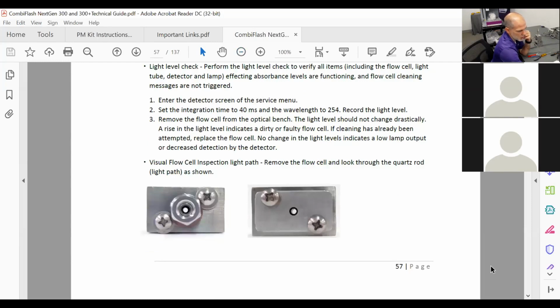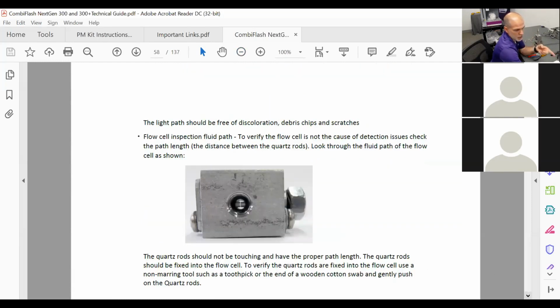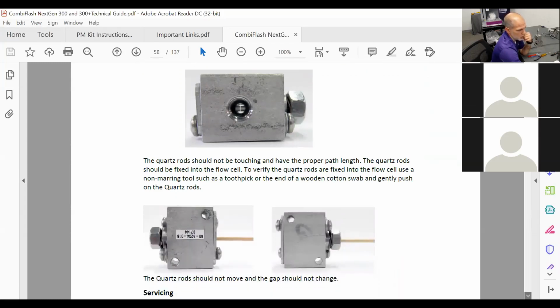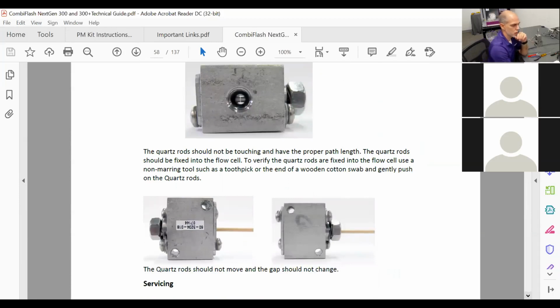Now what I'd like to do is these next couple parts here talk about how to take your flow cell out, how to check it. There you can see the gap in that picture. It's very small, it's 0.1 millimeter, but you should be able to see it with your eyes. All right, it's showing you how to press upon them with a Q-tip here or a wooden stick. And the reason for that is these rods are held in place with a glue. So if that glue has come apart or cracked or dried out, then these rods can move. Pushing on this very lightly on the side and checking the gap again lets you know if that glue is still good or not.